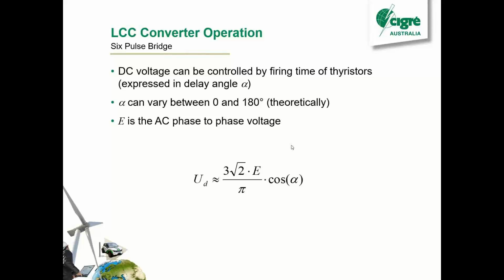when alpha is 0, which means we're basically firing the thyristor as soon as we can, we will get the maximum voltage. That voltage is called UDI naught, and it is 3 times √2 times the phase-to-phase AC voltage divided by pi. It comes out to about 1.35. So you just need to remember 1.35 times the phase-to-phase voltage. That'll give you your ideal DC voltage, no load.